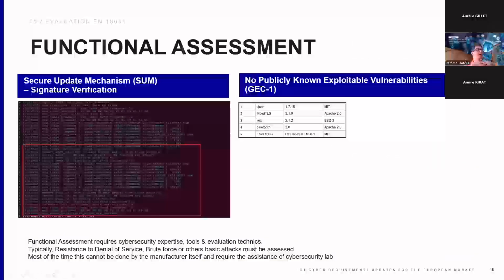The functional assessment itself requires the device to be available, along with its environment. For example, if you have a device configured with an application that's supposed to provide data to the cloud, then during testing we need a representative environment of the device, including the different accessories or cloud access, in order to check the exchanges and the different functions triggered, for example between the application and the device for setup and configuration, and in operational or maintenance mode, the different ways the device will interact with external entities.